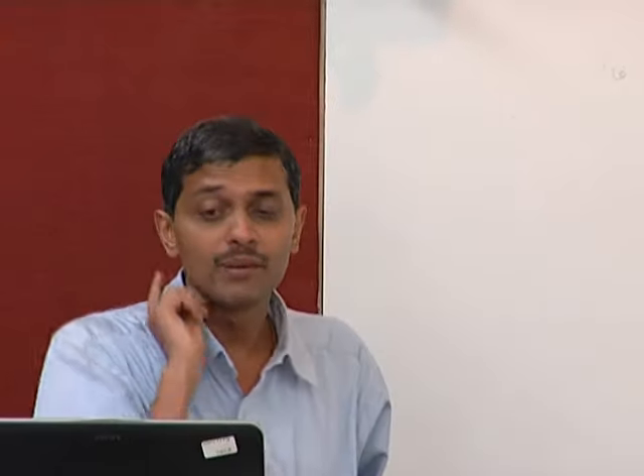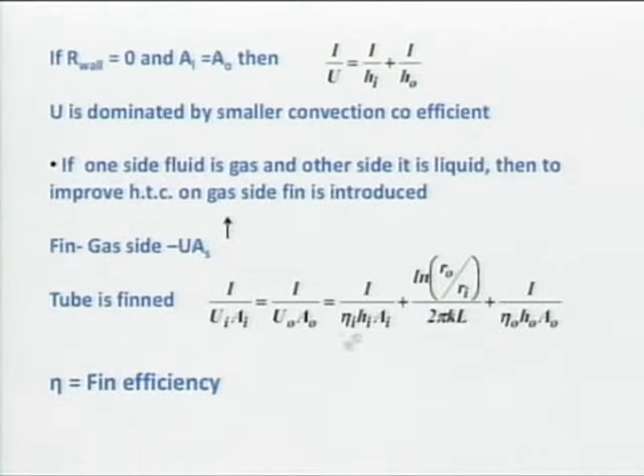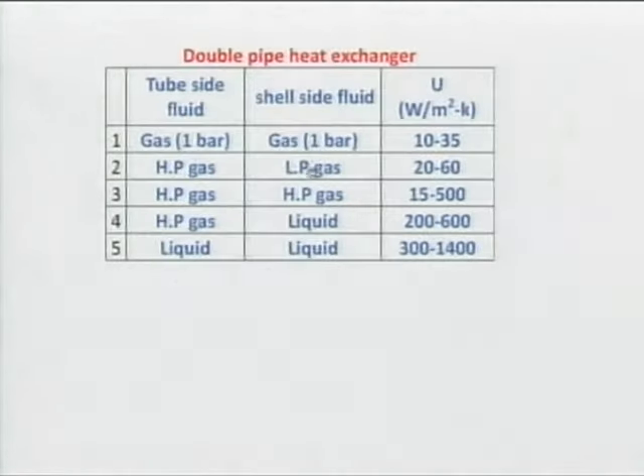We need to qualify whether the overall heat transfer coefficient is based on inner area or outer area. If I have fins, I will put the fin efficiency on both the inner side and outer side. These are the typical heat transfer coefficient values. For two-phase flow heat exchangers, you will have higher heat transfer coefficients. We need to spend time on fouling because students cannot easily realize its importance.